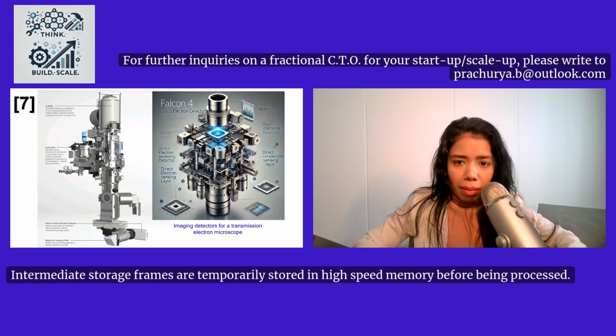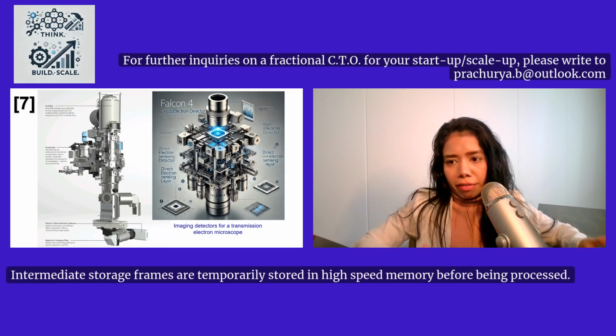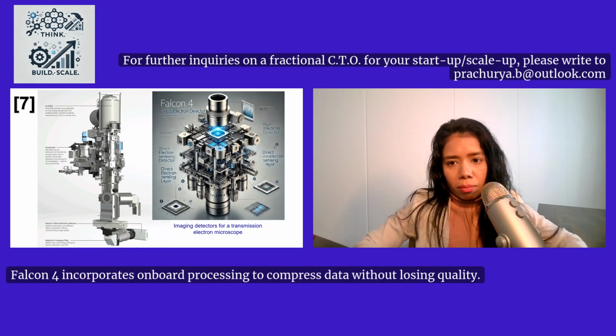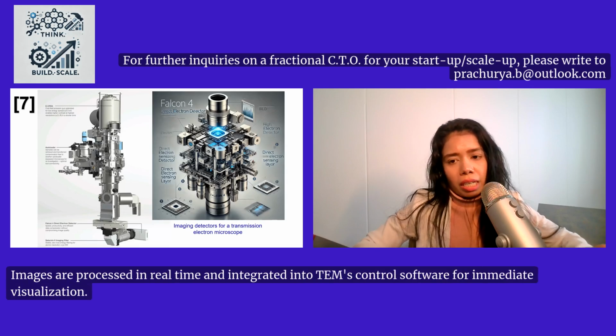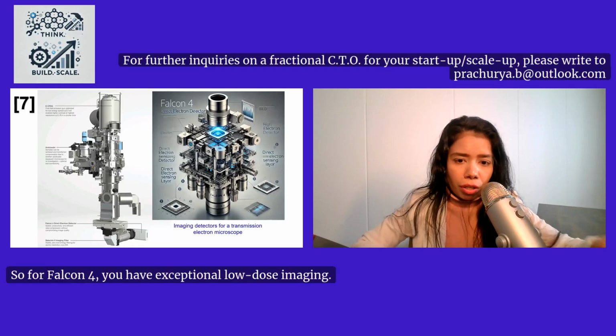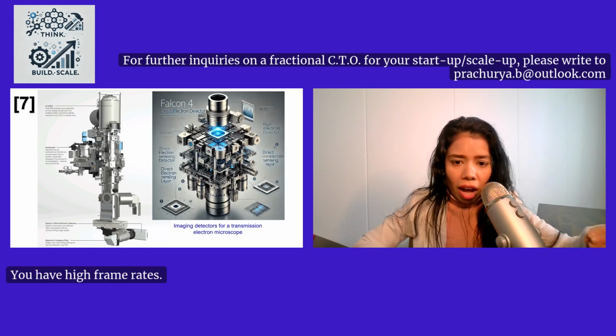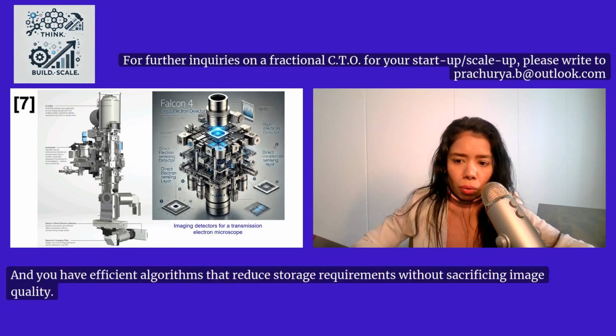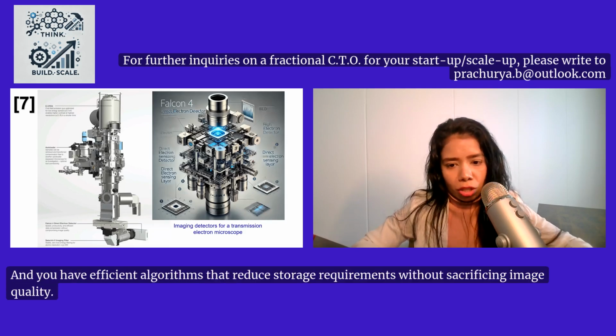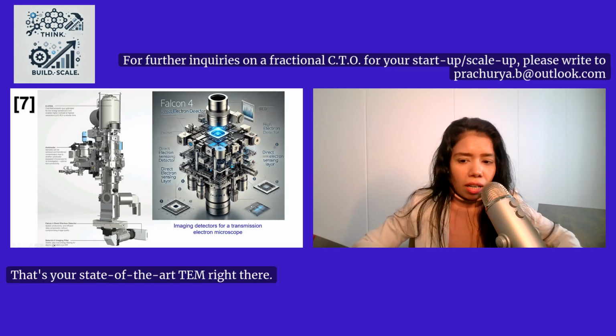Intermediate storage. Frames are temporarily stored in high-speed memory before being processed. Falcon 4 incorporates onboard processing to compress data without losing quality. Images are processed in real time and integrated into TEM's control software for immediate visualization. So for Falcon 4, you have exceptional low dose imaging, high frame rates, high pixel density, and efficient algorithms that reduce storage requirements without sacrificing image quality. That's your state-of-the-art TEM right there.